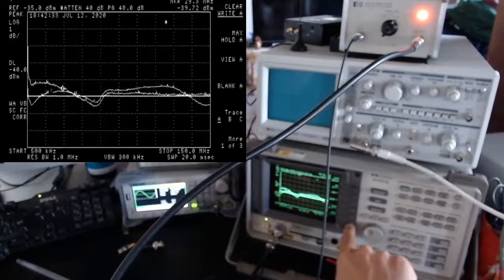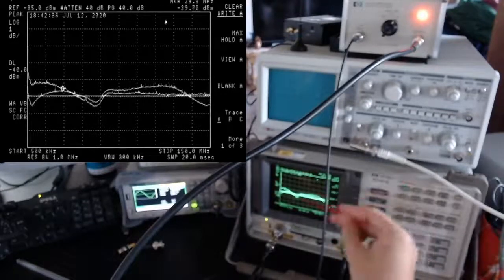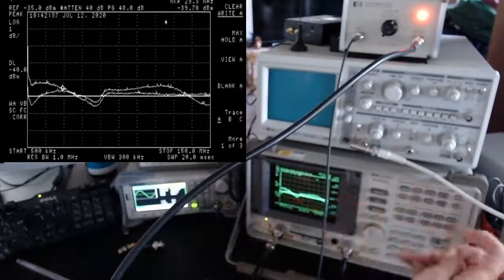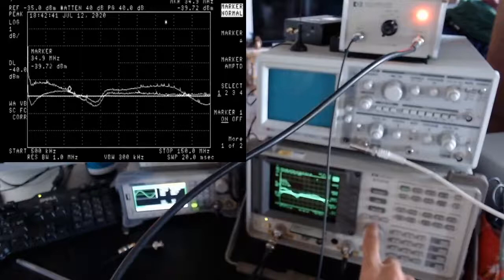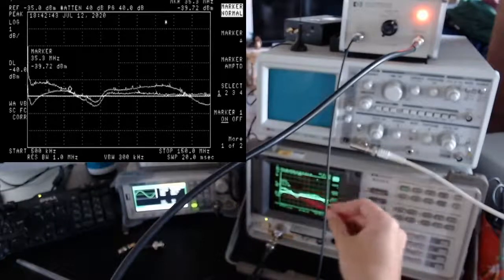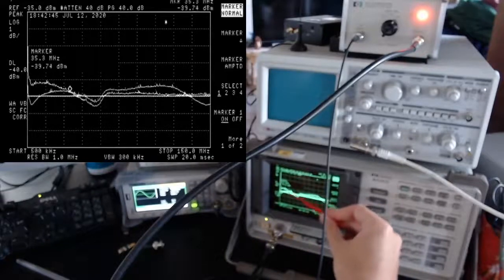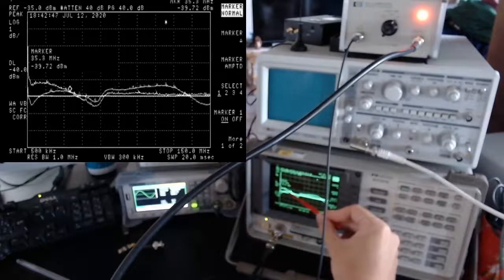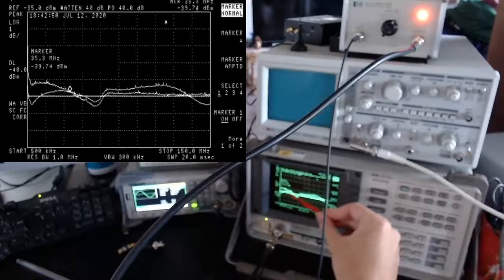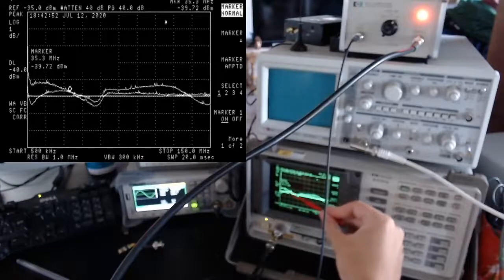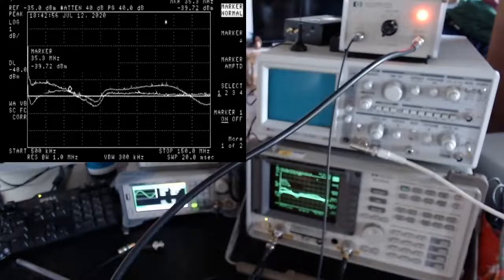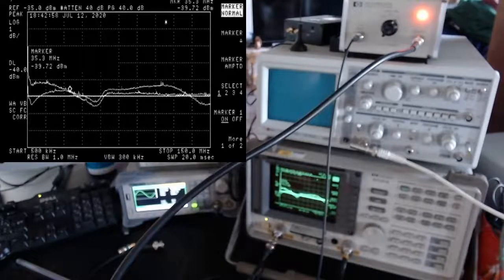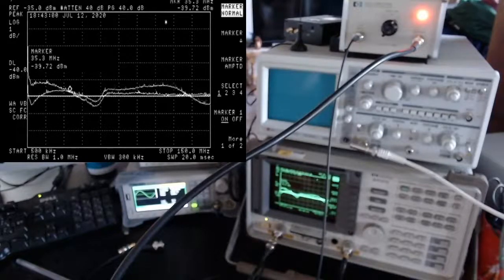So as you can see, for example, here around this point, we have basically around 35 MHz. We have that tracking generator and the response of the amplifier here are basically equal, which means that the amplifier in this point is doing a perfect 40 dB amplification.